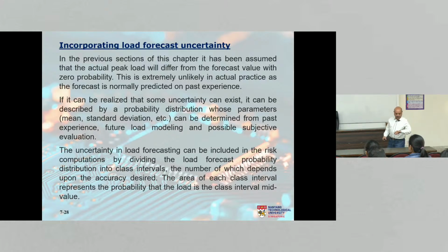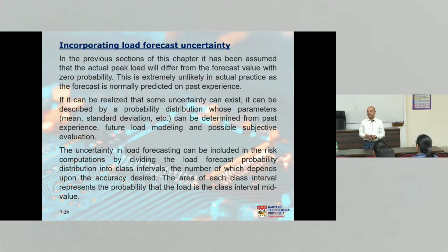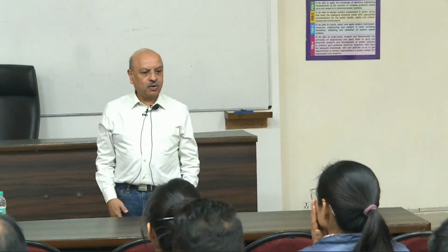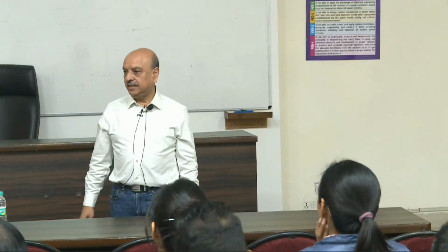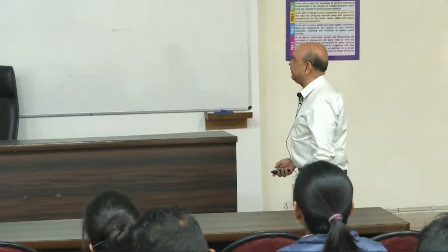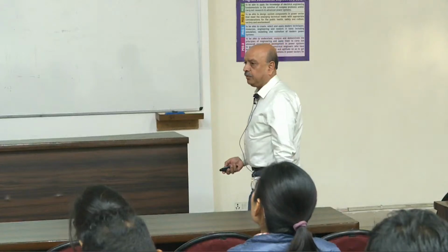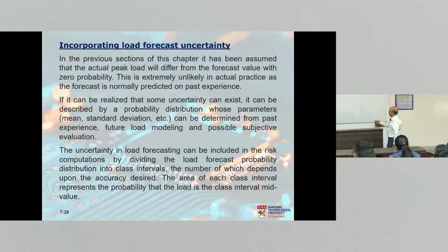Now, one more thing that we need to introduce is uncertainty in the load. We have so far been using 200 megawatt installed capacity and 160 megawatt peak load, right? But the peak load is not so certain. So how do you include the uncertainty in the load? We call it load forecast uncertainty, LFU, I'm going to use that acronym. We know that some uncertainty exists in the load, which is described by a probability distribution, okay?